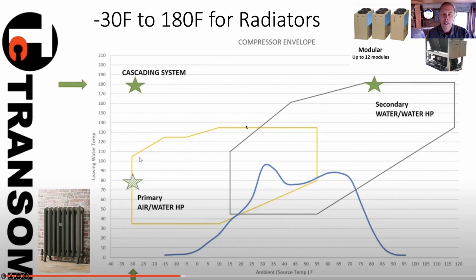Then you can take that 80 degree Fahrenheit water, which this product is happy to work with, and raise it up to 180 degrees Fahrenheit. This is a water source heat pump, so it's concentrating the heat - that's all, it's not making new heat. It's just squishing it into a smaller volume of water, which raises the temperature. So using a water source heat pump paired with an air source heat pump is a way of using all the normal refrigerants, R410A basically, and R134A, which are getting phased out quickly, just so you're clear. The products are already out on the market and there's already all the regulatory framework to phase them out. So you should get familiar with CO2.